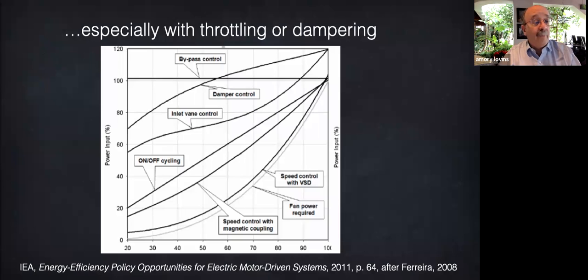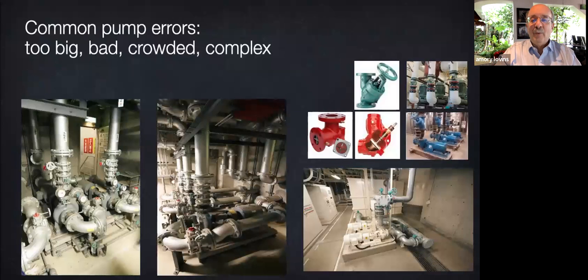And in the graphed example, if you drop from 100% to 20% flow, going from right to left, the damper control, which is the top curve for the airflow, cuts the fan power from 120 nominal units to 70. But taking out the damper and using ASD control, the bottom dark curve, goes from 104 fan power units down to 5. So same flow, smarter method, 93% less energy. Don't get in the way of the moving air, just don't move it as fast. Even good equipment is often installed poorly.